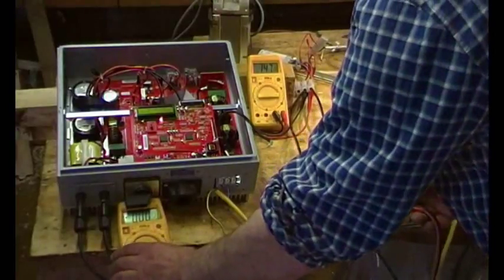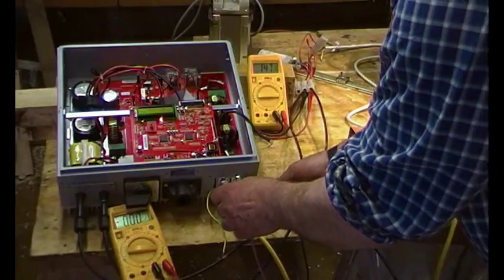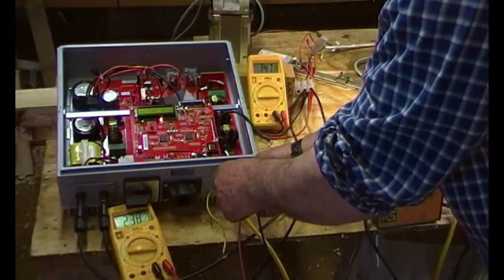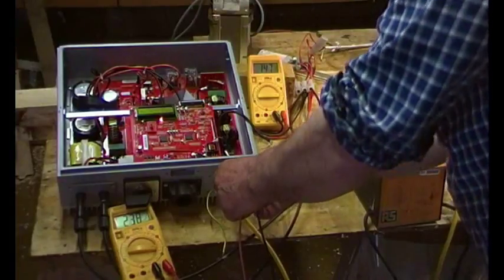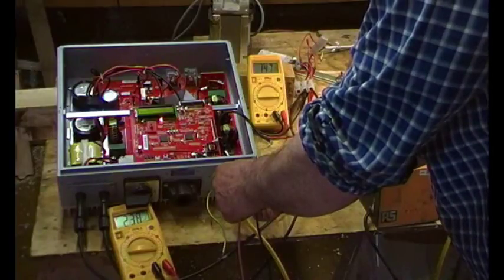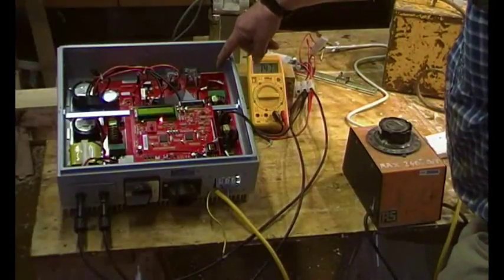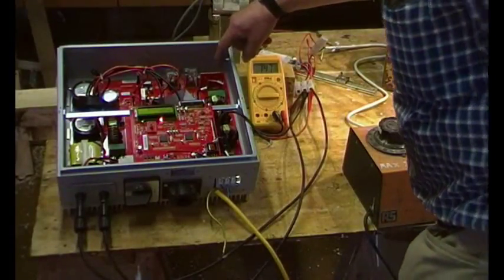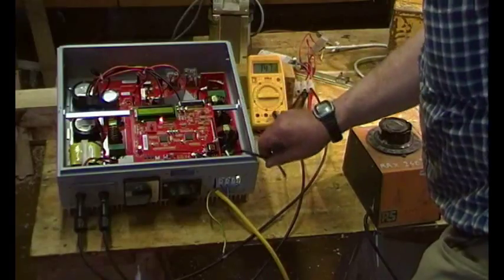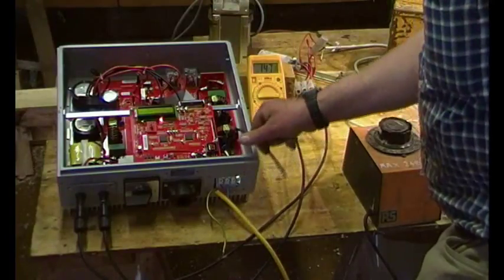So I'm just going to put this meter here, and that's set on 700 volts AC, and just to prove - 238 volts - so we do have mains there, but it's not getting through. That I think is the mains sensor, so we've got a problem there somewhere. There is a fuse down there. I have tested before, that will be a mains fuse, but there's nothing wrong with that.